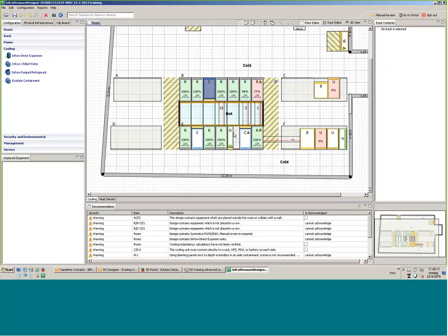I don't believe that I have problems. Very often this tool is not 100% exact, especially when I have a gap here. Even though the tool adds directly a blanking panel, we have today blanking panels for 300, 600, and 750 millimeter, the tool still sees it as a gap and allows air through that. So here, please be careful.